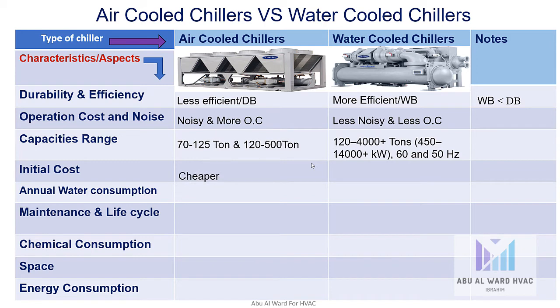The initial cost is cheaper for the air-cooled because it doesn't have the pumps and the condensing pumps, as well as the water cooler or cooling tower. That one is not available in the air-cooled chiller. That's why it is cheaper than the water-cooled for the initial cost, while the water-cooled is more expensive. Annual water consumption: the air-cooled are not reliant on water at all. That's why it is zero in the water consumption. While the water-cooled chillers depend on water, that's why they need plenty of water.